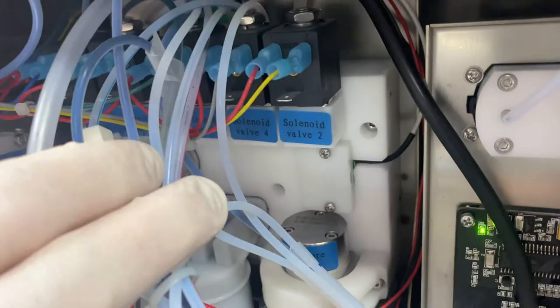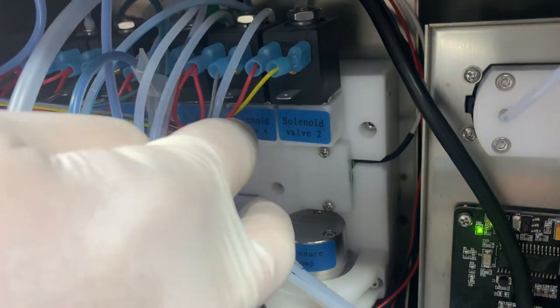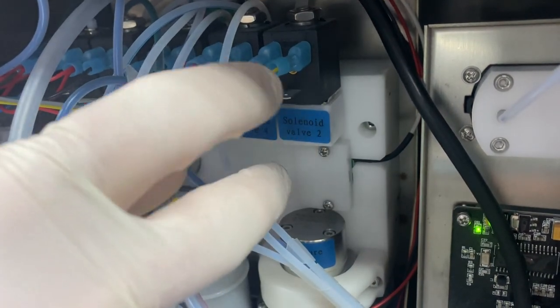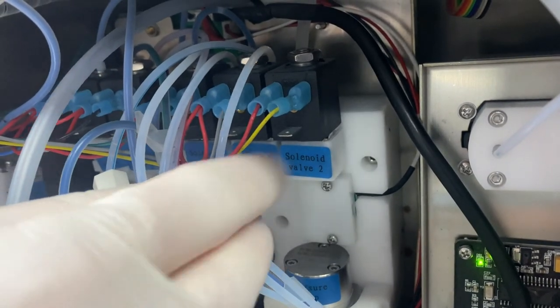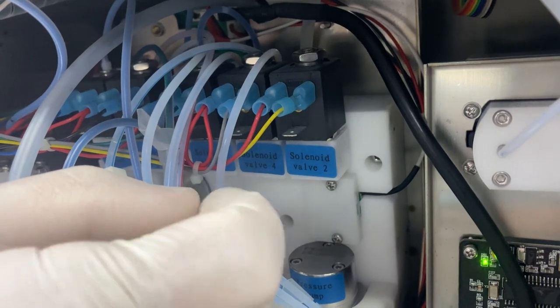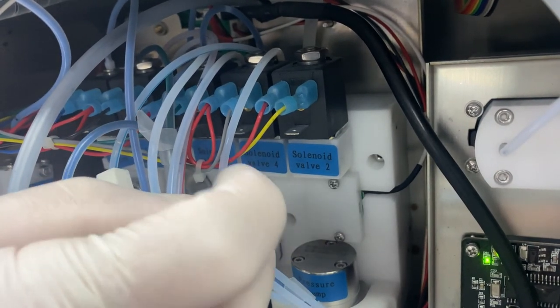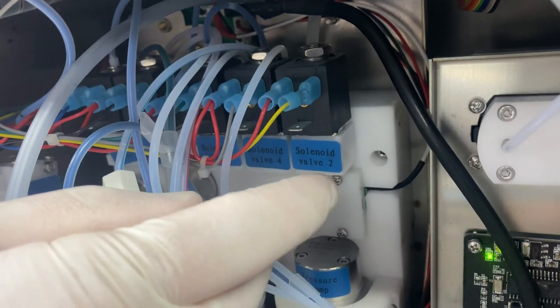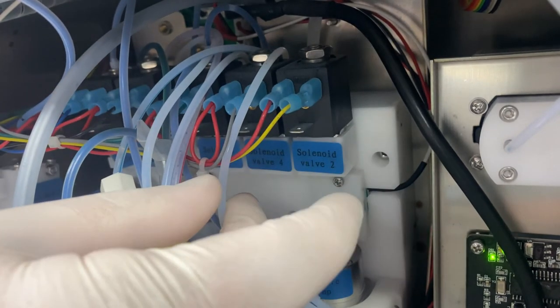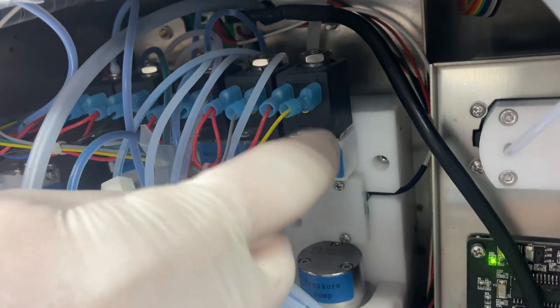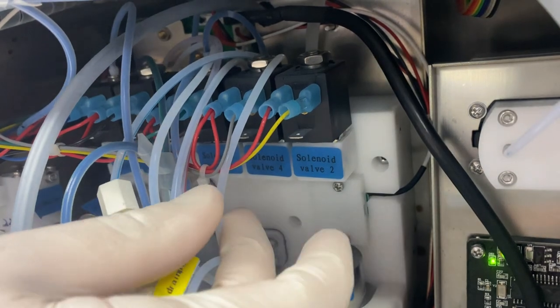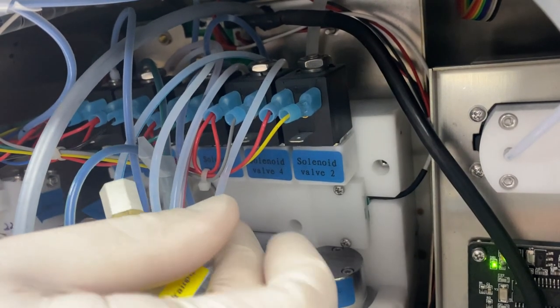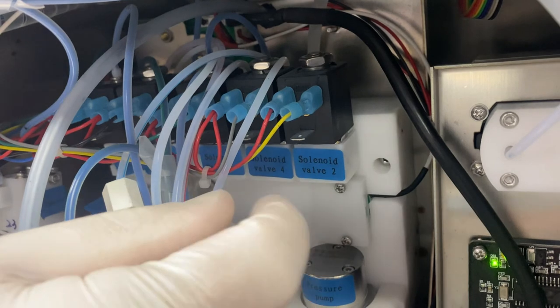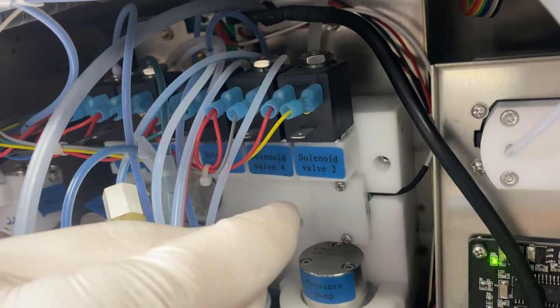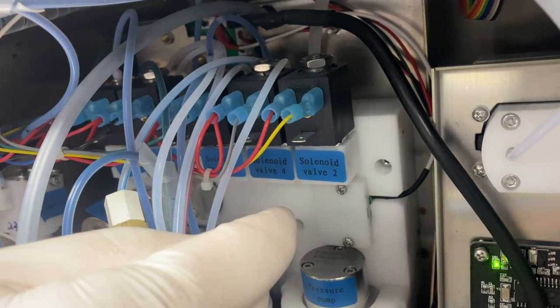We'll still take it apart just so you get an idea of what it looks like. So when we're troubleshooting valve two, or really either of the makeup valves here, testing power is exactly the same as what we did earlier in the video for valve six. Also, removing the valve from the manifold is exactly the same process as valve six, or any of the valves for that matter. So we're gonna go ahead and disconnect our leads, unbolt this from the manifold, and then we'll show you when we take it apart the slight difference in the plunger, and that's it.